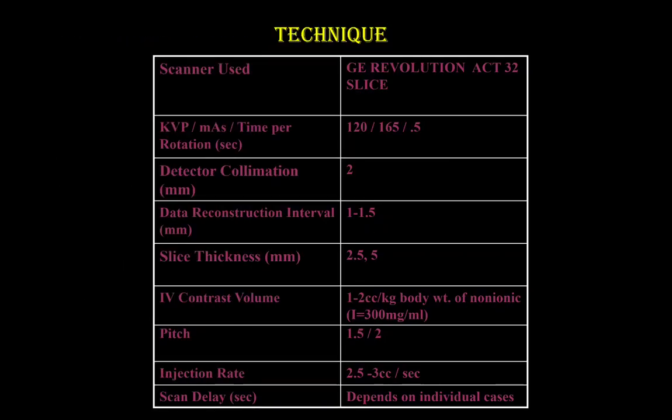The scanner used was GE Revolution ACT 32-slice. Standard KVP of 120 and MAS of 165. The detector collimation was 2 mm, slice thickness was kept around 2.5 to 5 mm, IV contrast volume was around 1 to 2 cc per kg, and the concentration was around 300 mg per ml.